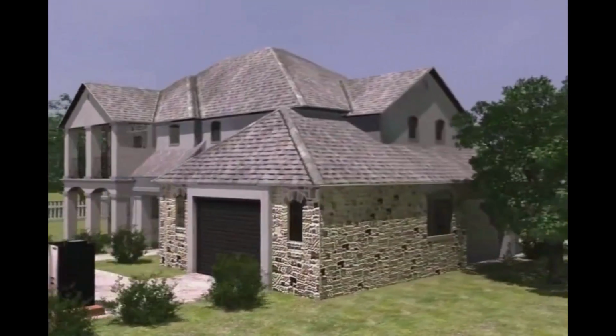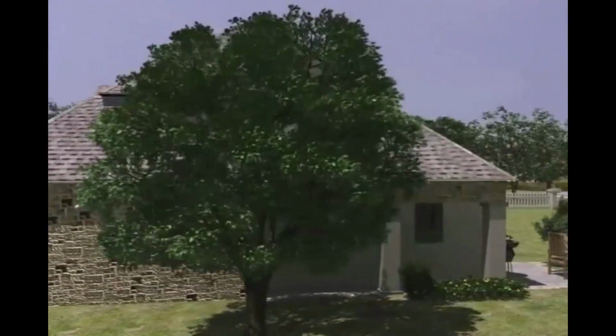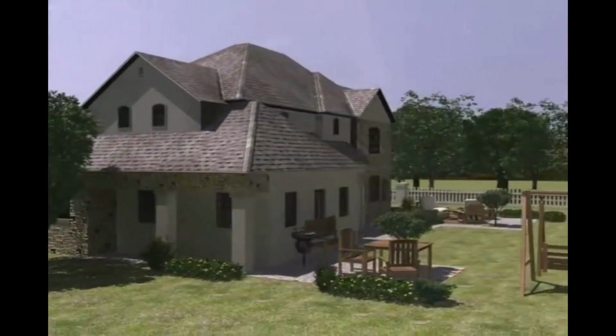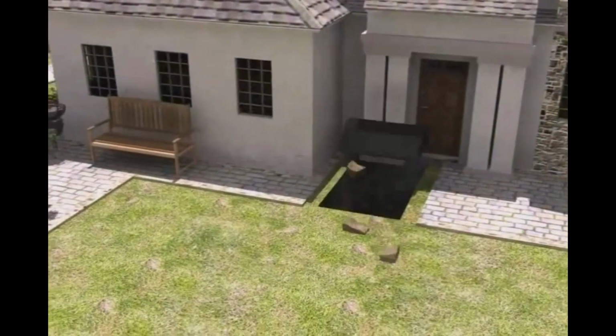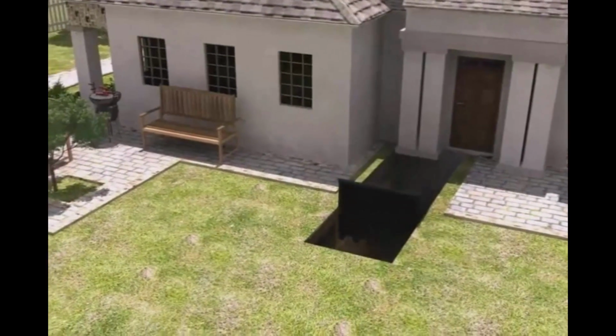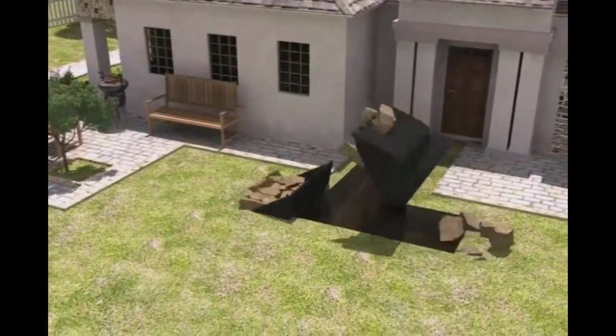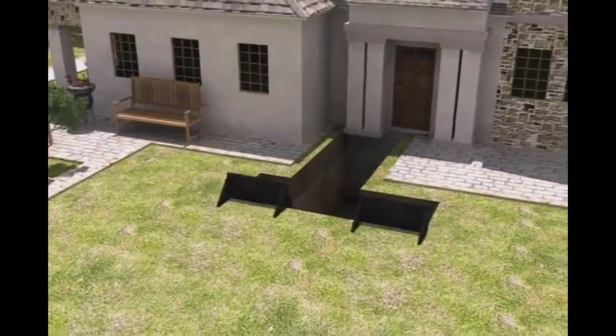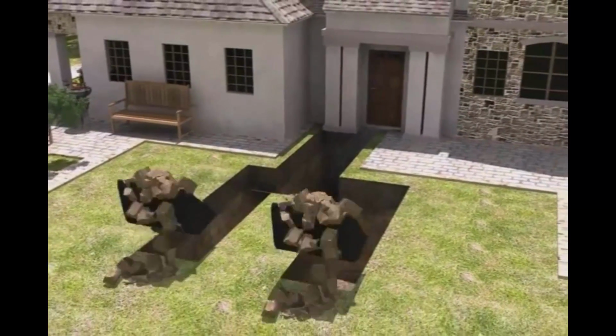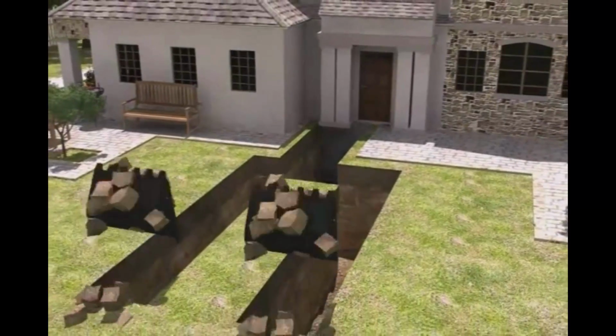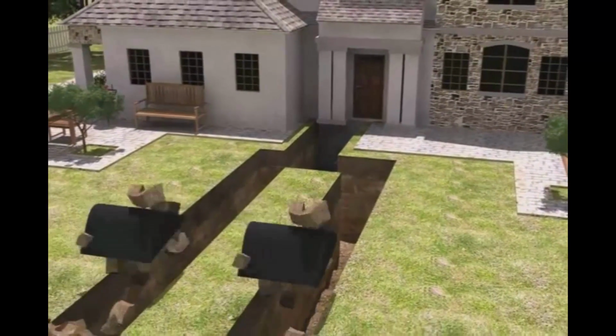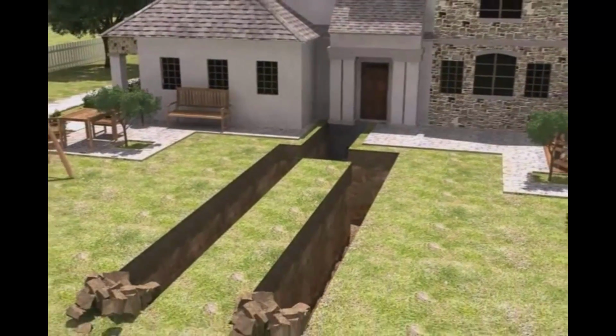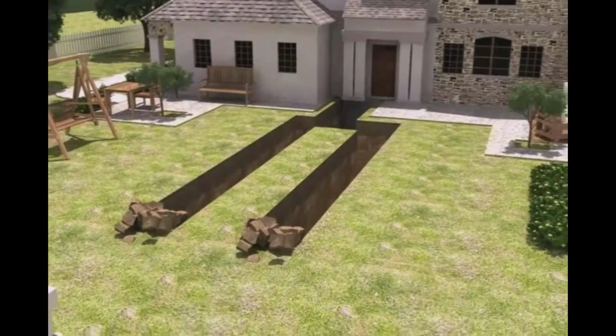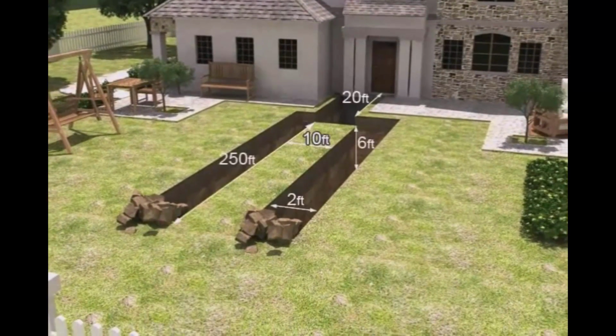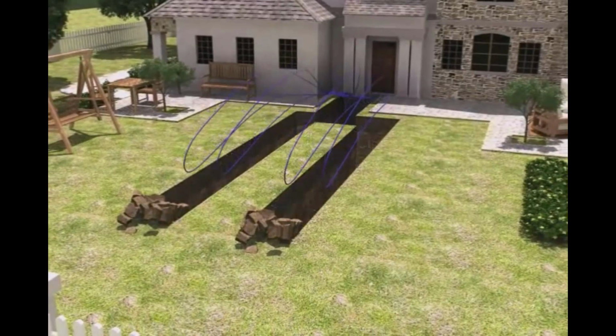Installation is accomplished in 4 easy steps. Installation of loops, manifold, plumbing, and electrical. The first step is the excavation of loop fields. The horizontal loop is the most common and needs around 250 feet of continuous trench as shown in this example. House size and BTU requirements will determine how many loops are needed. Available land will determine the type of loop required. We have included some common dimensions for this example.